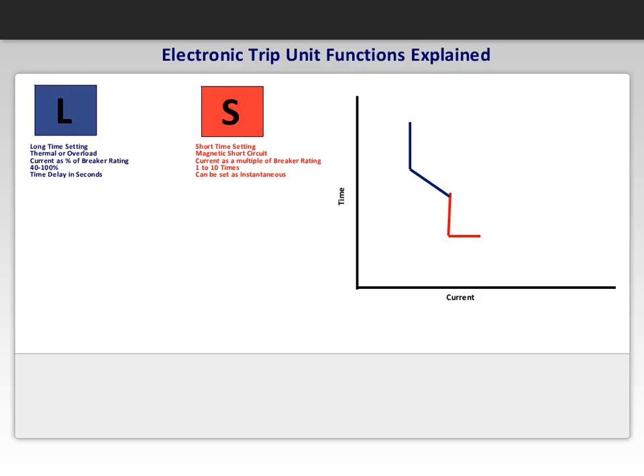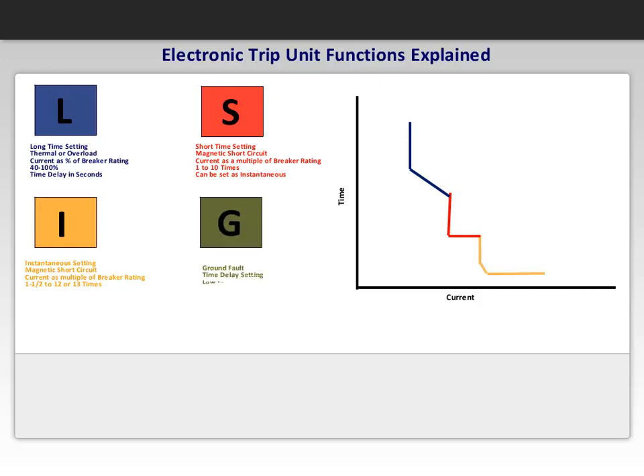The I covers the instantaneous setting. It involves the magnetic portion of the curve, represented by the yellow line. It allows for adjustment of 1.5 to 12 or 13 times the rating. Lastly is G, which represents the ground fault setting, which covers the settings for the low-level currents to ground and time delay settings, shown by the green line on the curve. This flexibility allows the customer to coordinate the protection needed for all circuit breakers in the building system.